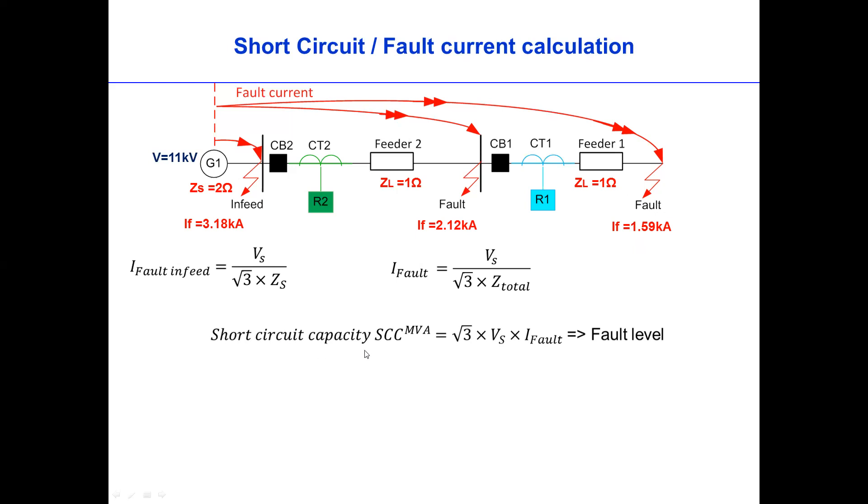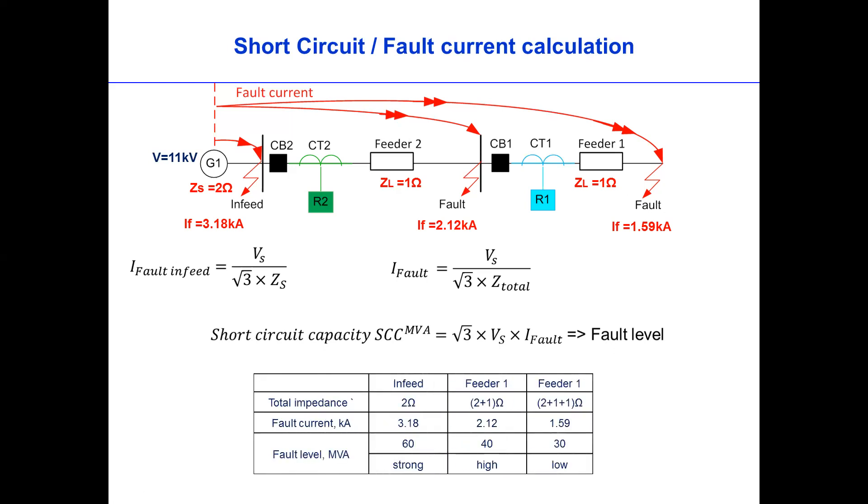In another way, we can also calculate the short-circuit capacity in MVA. That is about root 3 times voltage at the fault point times the fault current at the fault point as well. That is what we call fault level.